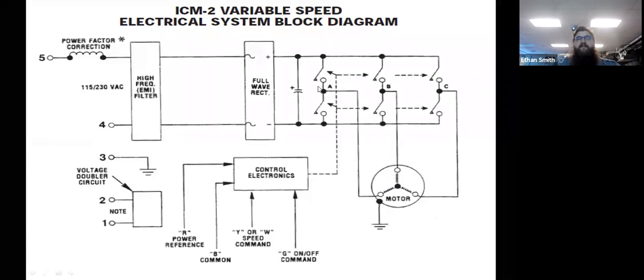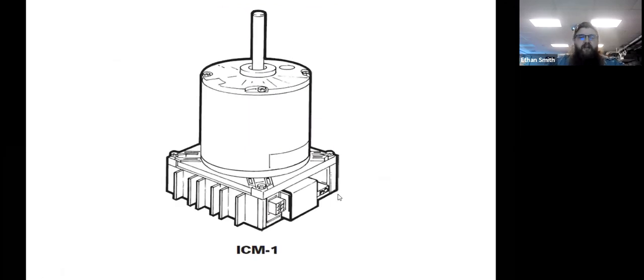Okay, so this is how all variable speed systems operate in the HVAC market. There's some version of this going on, and there's usually a 3-phase motor downstream. So when we talked about those motors that we just had, when we were doing the generator demonstration, that's what these are. These are variable speed motors out of a furnace. Okay. So that all started back with the ICM-1.